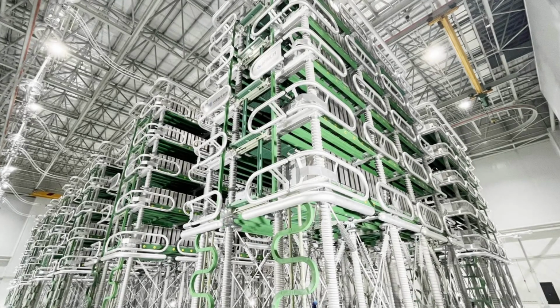When it reaches the destination grid, a second converter station takes that flat DC power and inverts it back into AC power, mathematically perfectly matched to the exact phase of the receiving grid. These HVDC systems aren't just dumb pipes. They are the ultimate grid stabilizers, able to precisely control power flow in either direction within milliseconds, providing synthetic inertia and voltage support to whichever grid is under stress.